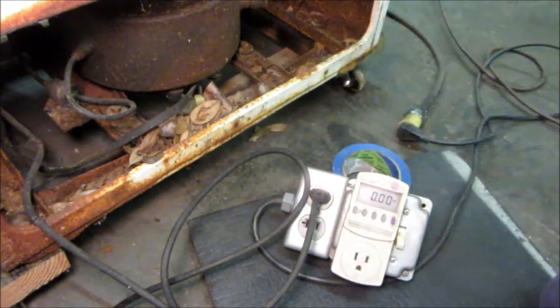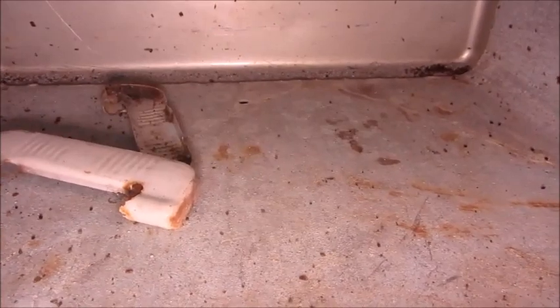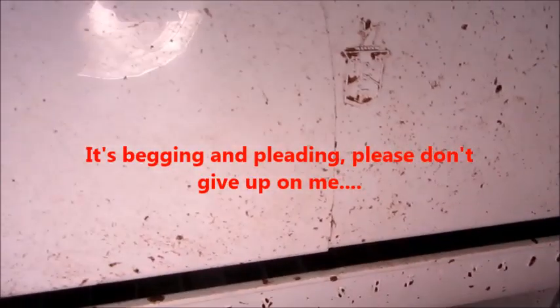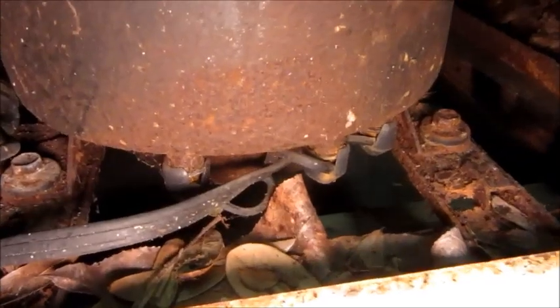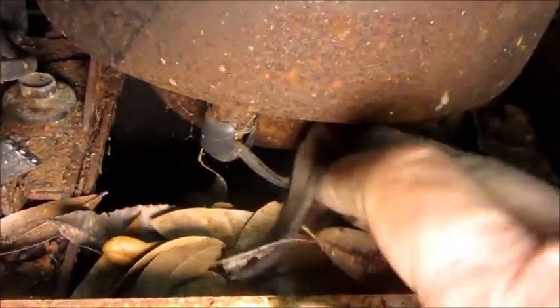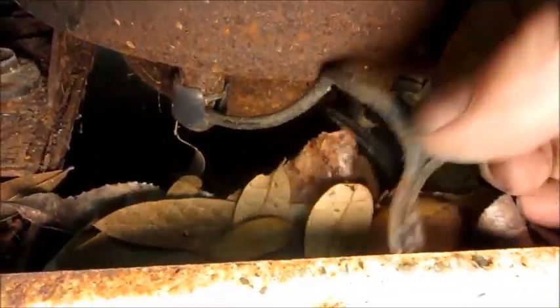In that case, go to plan B and hook up directly on the compressor. After that short run attempt, I hear some noise in there — at least there's something in there. But I'm pretty sure this is why it didn't successfully start. All I can say is these terminals look terrible. I don't really know if I'm going to be able to get them off or not. In the interest of checking the compressor out, I'm probably going to just cut back this cable, strip it, and get alligator clips on it. Then assuming the compressor is viable, I'll work on making proper connections.